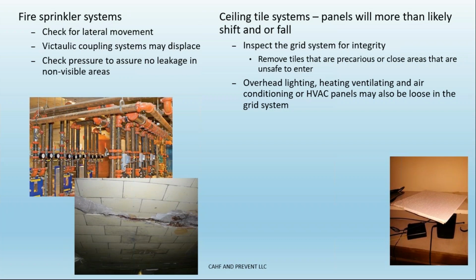For your fire sprinkler systems, check for any kind of lateral movement. The Victaulic couplings may displace. Most are designed for 10% or 15% displacement. Sometimes this may be compromised. Make sure you have no leakage in any visible areas and non-visible areas.